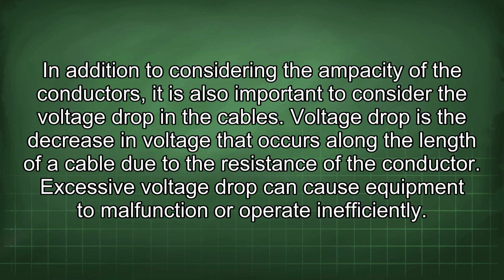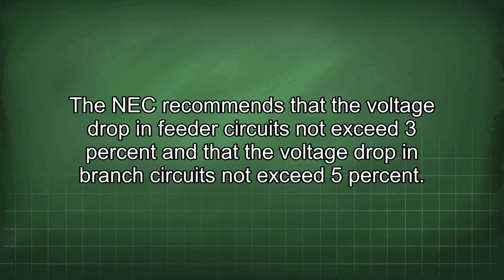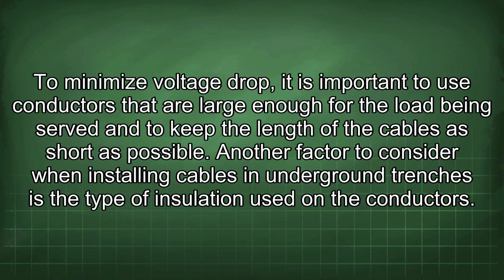In addition to considering the ampacity of the conductors, it is also important to consider the voltage drop in the cables. Voltage drop is the decrease in voltage that occurs along the length of a cable due to the resistance of the conductor. Excessive voltage drop can cause equipment to malfunction or operate inefficiently. The NEC recommends that the voltage drop in feeder circuits not exceed 3% and that the voltage drop in branch circuits not exceed 5%. To minimize voltage drop, it is important to use conductors that are large enough for the load being served and to keep the length of the cables as short as possible.